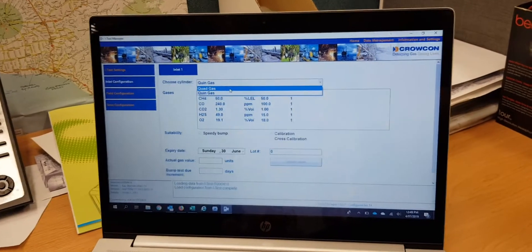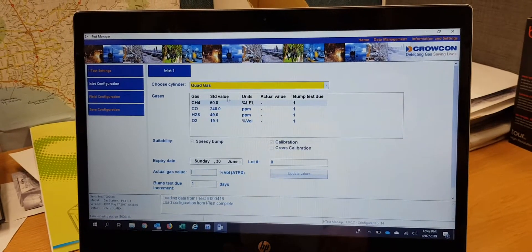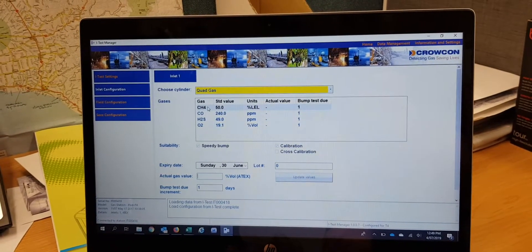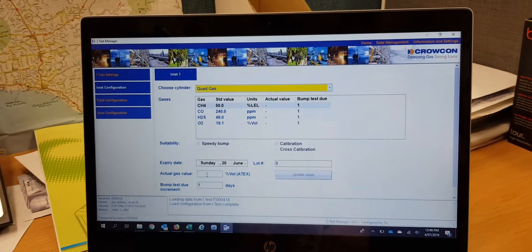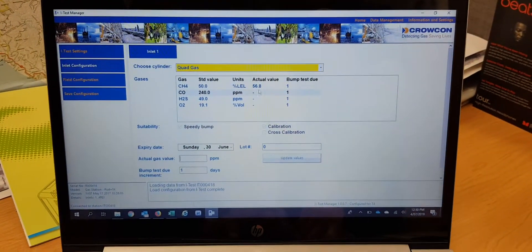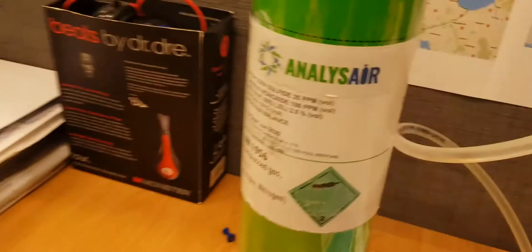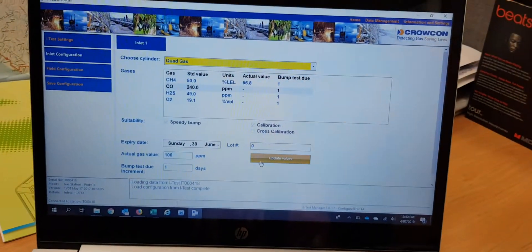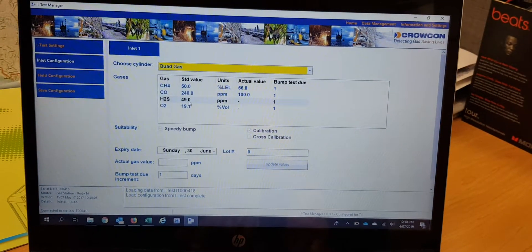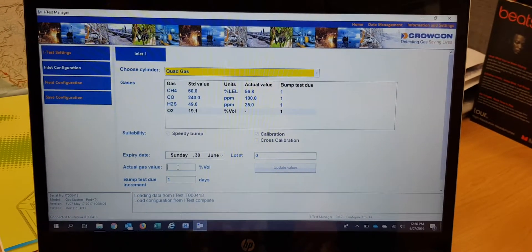Quad is four gas and Quint is five gas, so we use Quad. The accurate value of CH4 is 2.5% volume. We update the LEL value to 56.8% LEL, CO is 100 ppm, H2S is 25, and oxygen is 18.